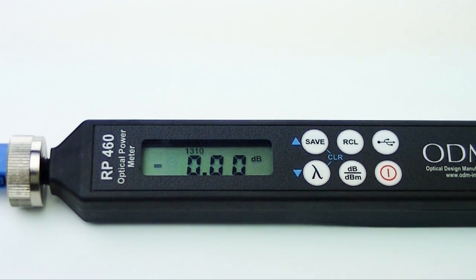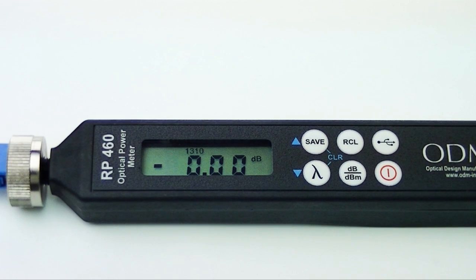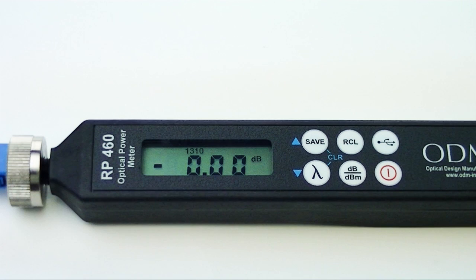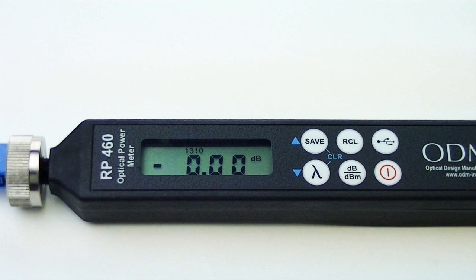You should now have a reading of 0 dB on your screen. Fluctuations of 0.05 dB in either direction are normal, but if the reading fluctuates much more than that, you will have to clean your connectors and try again.